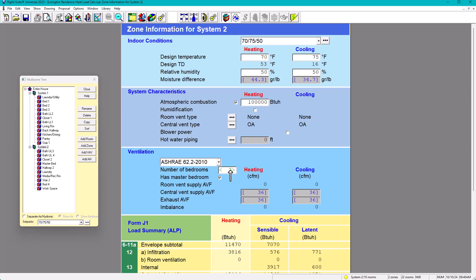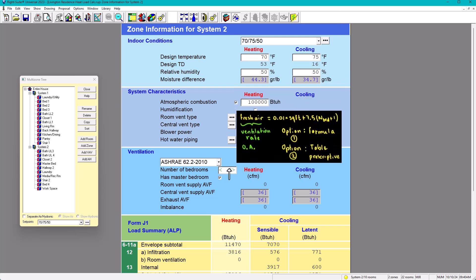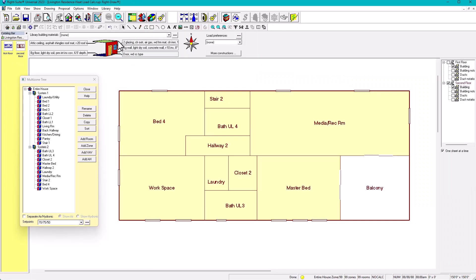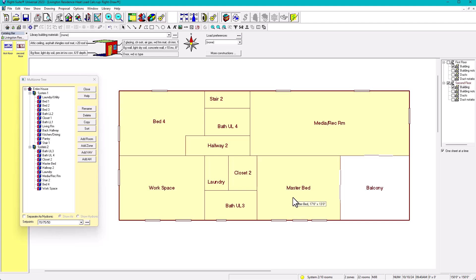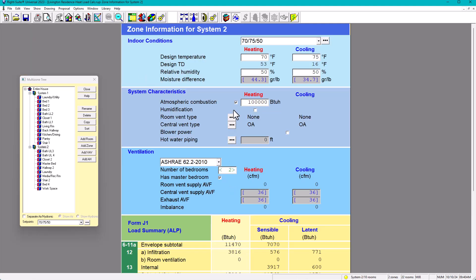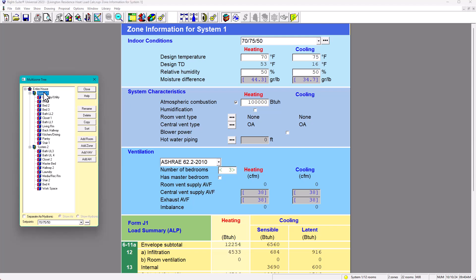When you check 'Has Master Bedroom,' the program adds one more occupant to the calculation. The formula is: 0.01 × square footage + 7.5 × (number of bedrooms + 1). The plus one accounts for the master bedroom, since husband and wife are two people rather than one. Without the master bedroom checkbox it counts one occupant per bedroom, but with it checked it adds an extra occupant. So System 1 has three bedrooms with no master bedroom, and System 2 has two bedrooms with master bedroom checked.